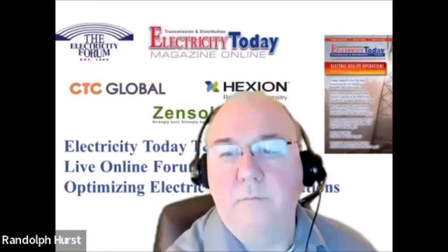But they still have, on top of that, what I would call flexible capacity, for running whatever period of time they need. It's not an emergency rating like, okay, I can do this for 2 hours, or I can do this for 200 hours over the life of the line. No, these are rated. So you can run at that 2x for an indefinite period of time, provided you've got the capacity to handle it in other parts of your system. Okay, great.